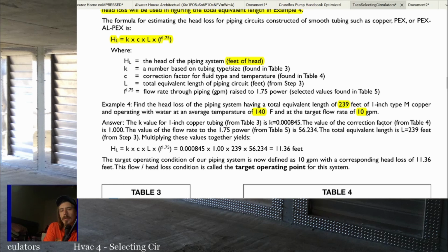You would determine that based on, if you were selecting radiators, it'll say this size radiator can handle this many BTUs at 180 degrees and this many BTUs at 160 degrees, and so on and so forth. Obviously, the lower temperatures are generally going to end up being more efficient, especially if you're talking about condensing boilers and stuff like that. The lower the temperatures you run at, the more efficient it can run. But a lot of times it's just based on what you're working with. Designing at a higher temperature will let you use smaller baseboards, smaller boilers, fewer loops in your radiant heat. But with lower temperatures you can design the system more efficiently, but you'll need bigger radiators, bigger baseboards, things like that. So in this system, they're designing for 140, which is a pretty common temperature, right?